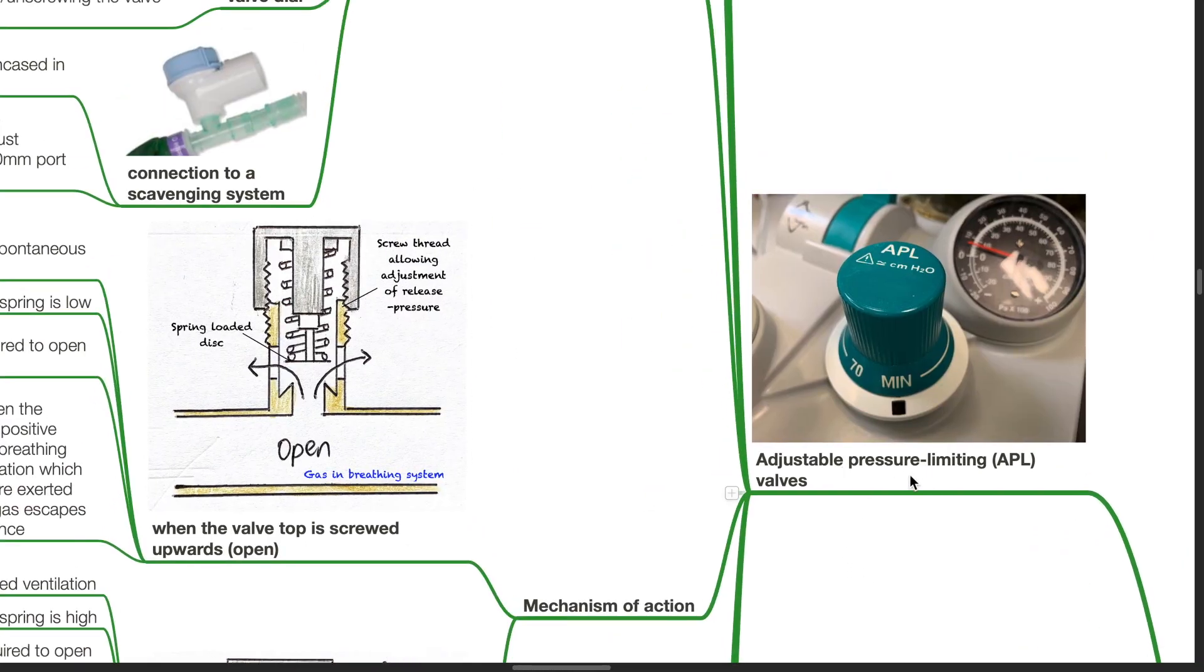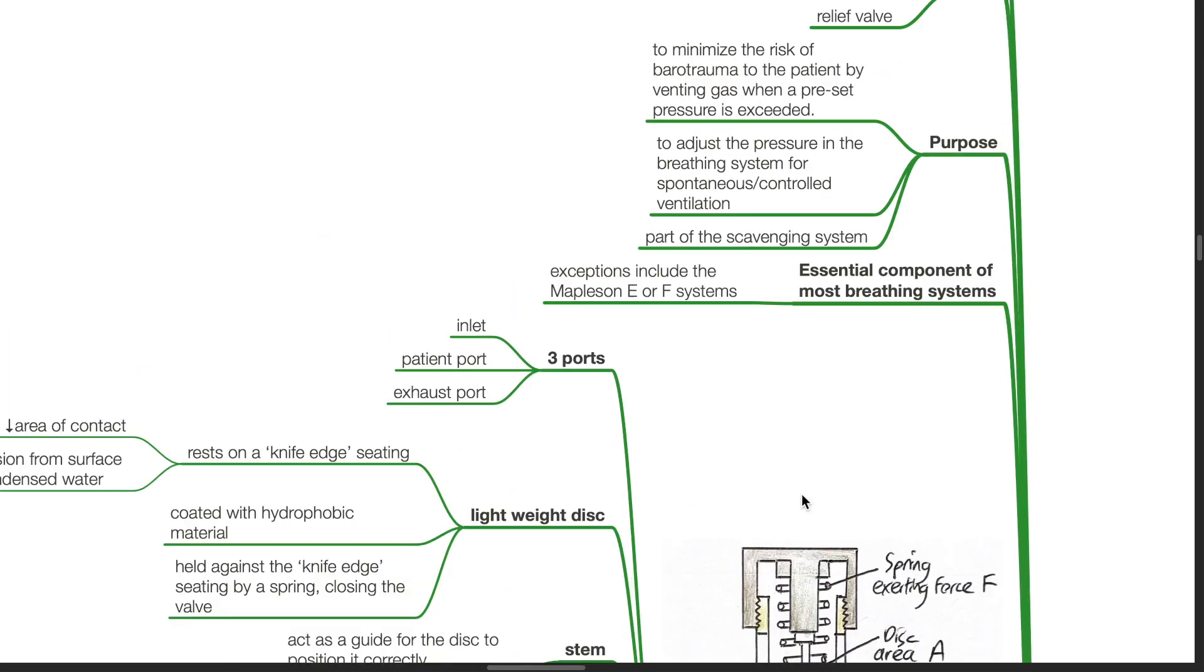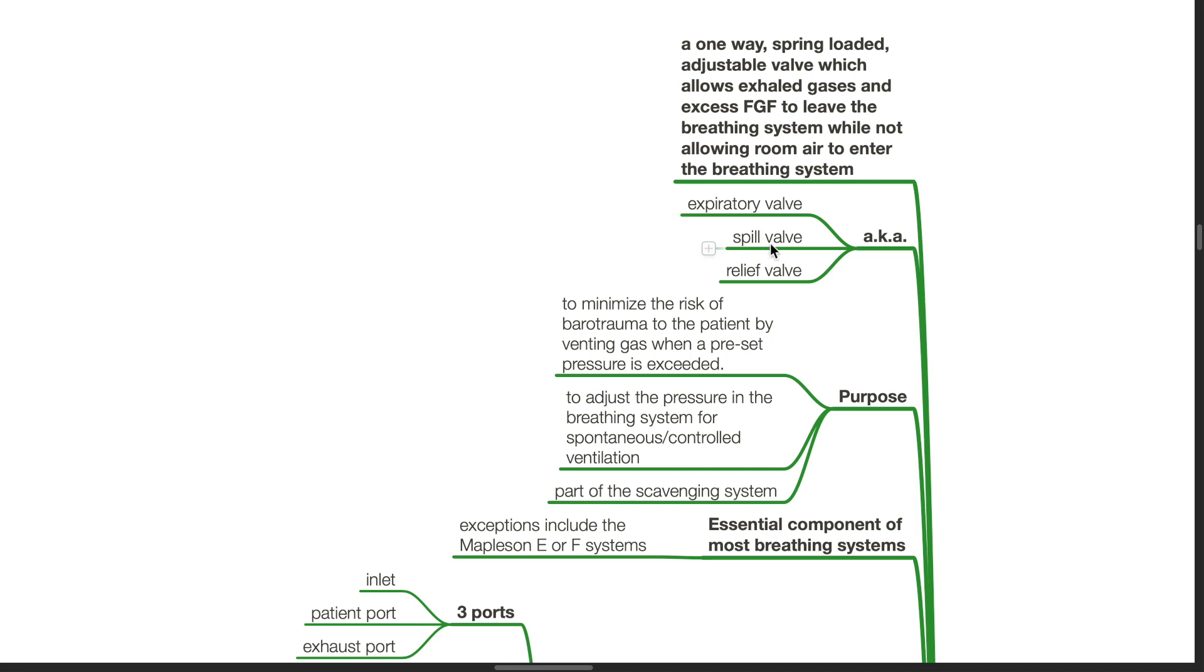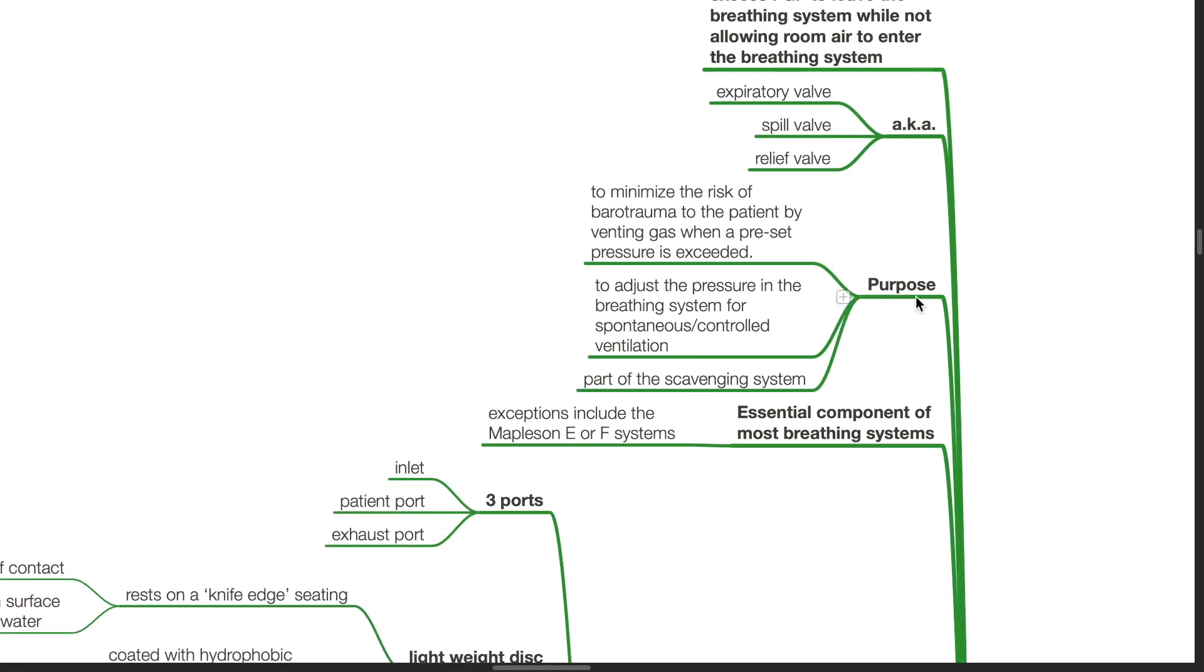Adjustable pressure limiting valves or APL valves. This is a one-way spring-loaded adjustable valve which allows exhaled gases and excess FGF to leave the breathing system while not allowing room air to enter the breathing system. It is also known as the expiratory valve, spill valve or relief valve. Purpose: the APL valve is used to minimize the risk of barotrauma to the patient by venting gas when a pre-set pressure is exceeded. It is used to adjust the pressure in the breathing system for spontaneous or controlled ventilation. And it forms a part of the scavenging system. It is an essential component of most breathing systems. Exceptions include the Mapleson E or F systems.